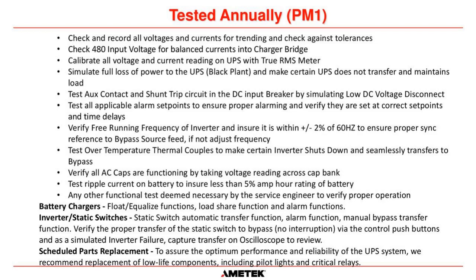We also recommend that you check all of the alarm set points inside your UPS. You have to make sure that your alarms are going to work correctly, just in case they are needed. So during the annual PM, we do all of that. Another important point is the free running frequency of the inverter. Now, a lot of people will say, okay, but you check the output of the UPS and it's running at 60 hertz. That means it's fine. Well, that's not actually true.